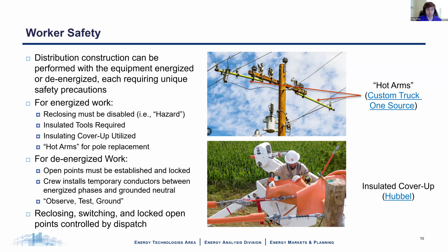For energized construction, line crews are also using insulated tools. They're using cover-up insulation, which is pictured there on the bottom. And if they're doing a pole replacement energized, which is a thing you can do and happens all the time, they'll use what are called hot arms, which are those little yellow fiberglass things off to the left and right on this pole, to physically move the conductors out to either side to give them enough space to work in the middle so they can raise the new pole, transfer everything over, take the old pole out. So a lot of construction happens energized because taking an outage is always a bad thing for customers and we try to avoid that whenever it's feasible to do so.